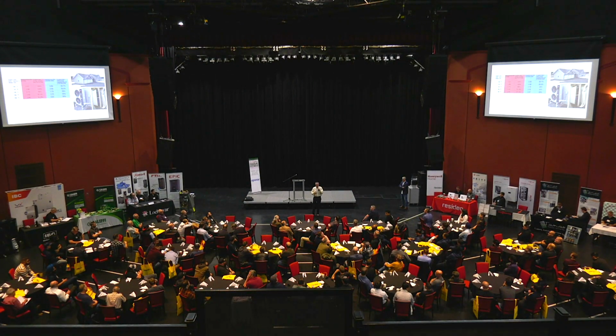Now, there's things you can do to bring those performance numbers up. You can insulate the building. Anything that brings the load down will bring the water temperature requirement down and bring the performance of the heat pump up. The other thing is you can add heat emitter surface area, as Robert was saying. The more surface area you have, whether it's baseboard, panel rads, radiant ceiling, whatever, it can be a combination of these emitters. As you increase total surface area of your emitter system, the water temperature goes down. And you may have opportunity to modify those distribution systems by adding more heat emitters. You may have opportunity to weatherize the building, or maybe it's a combination.